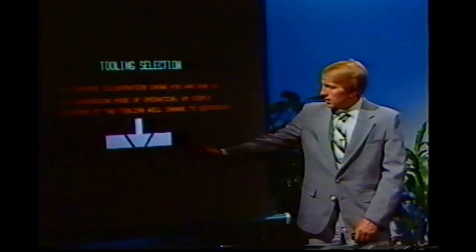So for instance, if we did have diverging tooling in versus converging, all the machine operator would need to do is come up, touch the picture, and we would automatically change to diverging mode of operation. Then the machine would be allowed to run. If the correct tooling is not chosen for the control system, the machine could be inhibited to run through the relay ladder diagram. This is just showing one way how a graphic representation can be used to tremendously aid a machine operator with the MACO8000.